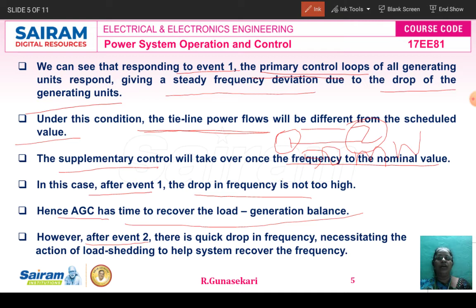Okay, now the supplementary control will take over and restore the frequency to the nominal value. So after event 1, the frequency drop is not too high. Already we saw this in the characteristics curve, frequency versus time curve. Now the automatic generation control has time to recover the load generation balance. Therefore after event 2, there is a quick drop in the frequency. So we have to take the necessary action of load shedding, which helps the system recover the frequency. That is the emergency control. Okay, then this is the first issue.